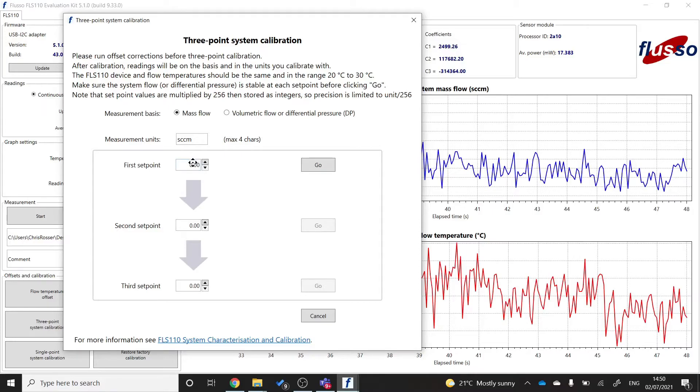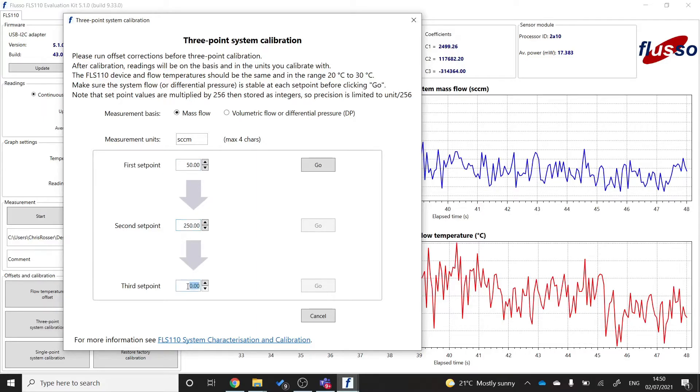So 10% for me is going to be 50 SCCM. 50% of my range is going to be 250 SCCM. And 90% of my range is going to be 450 SCCM. Once I have those set, I'm going to set my mass flow controller to 50 SCCM, the first set point.